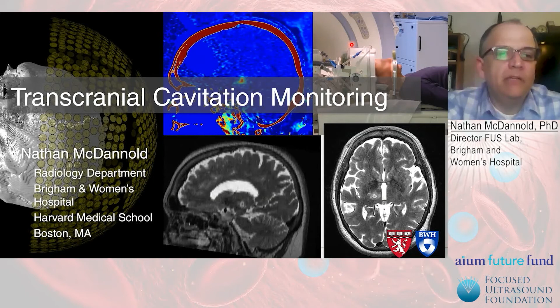The first is transcranial thermal ablation. This is done with the Exablate Neurosystem from InSightec, as you can see here. In this helmet, we apply thermal ablation in the brain with transcranial sonication, and the cavitation detectors are built into the helmet. And this is an FDA-approved treatment for thermal ablation in the thalamus for tremor, and it uses active control based on acoustic emissions.